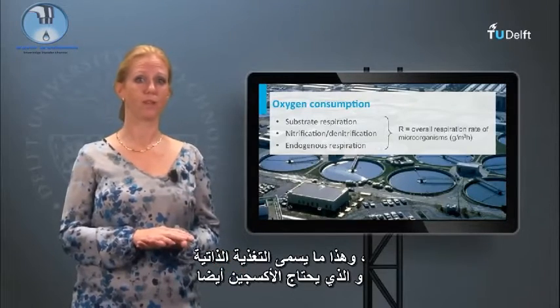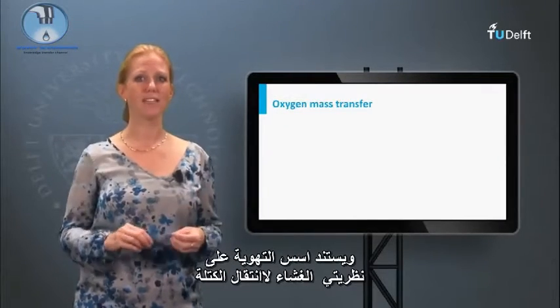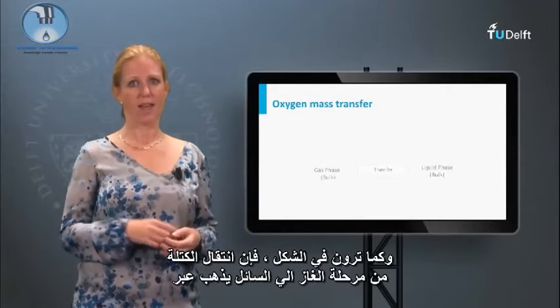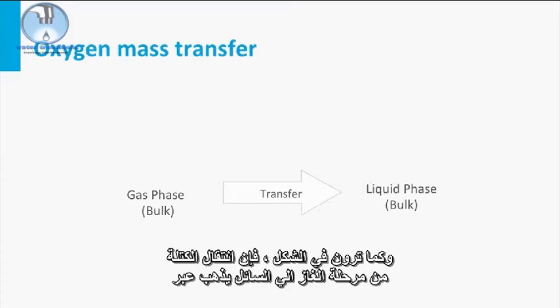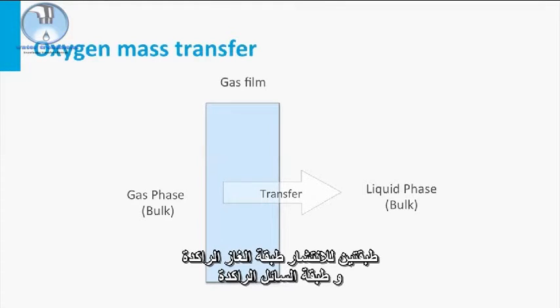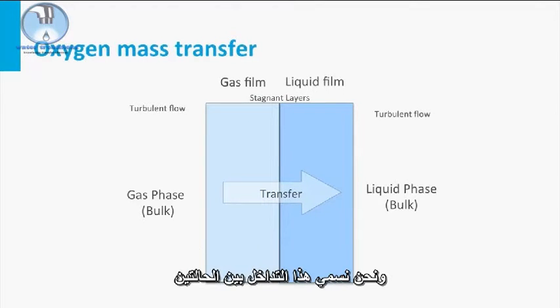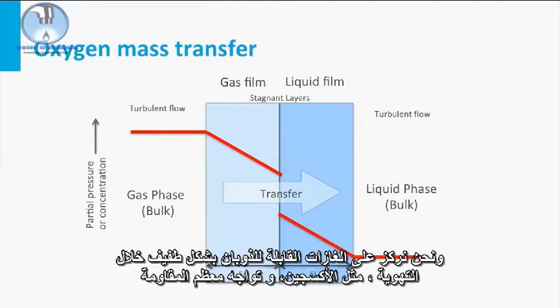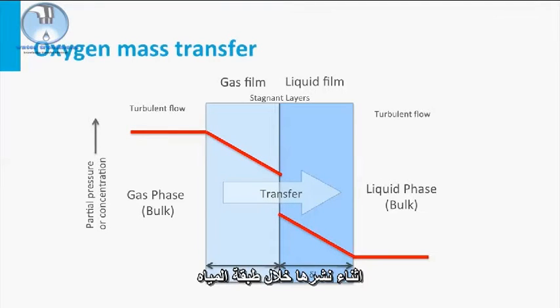This is called endogenous respiration, which needs oxygen too. The basics of aeration is based on the two-film theory of mass transport. As you can see from the figure, the mass transfer from the gas phase into the liquid goes via two diffusion layers: the stagnant gas film and the stagnant liquid film. We call this the interface between the two phases. Slightly soluble gases like oxygen encounter most resistance diffusing through the water layer.